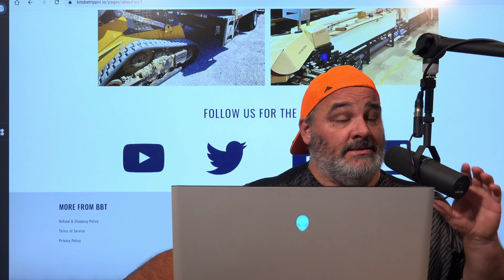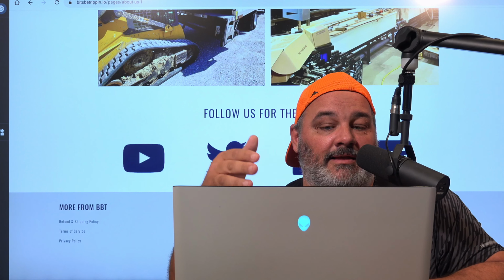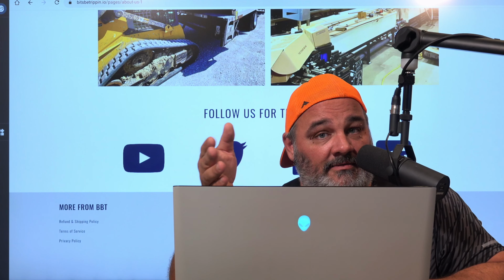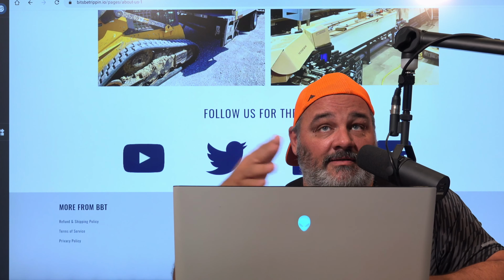As an example, some machine selection typically is what's your hash cost per terahash, and what's your replacement cost of parts. That's another piece. What parts are available? Can you get fans relatively cheaply? Can you get power supplies without spending $300-$400 per power supply, that kind of thing? So you're going to go through these things, especially at scale. You're going to definitely go through them. In just the 6 months that we've had, we're close to 40 power supplies out of 1,400 machines.